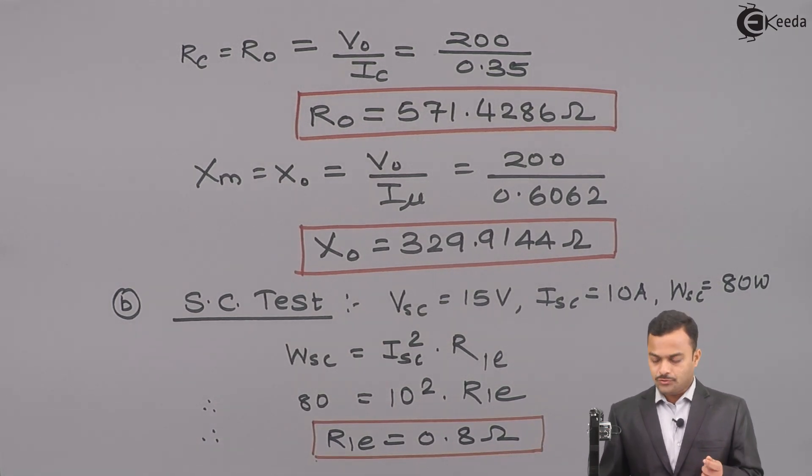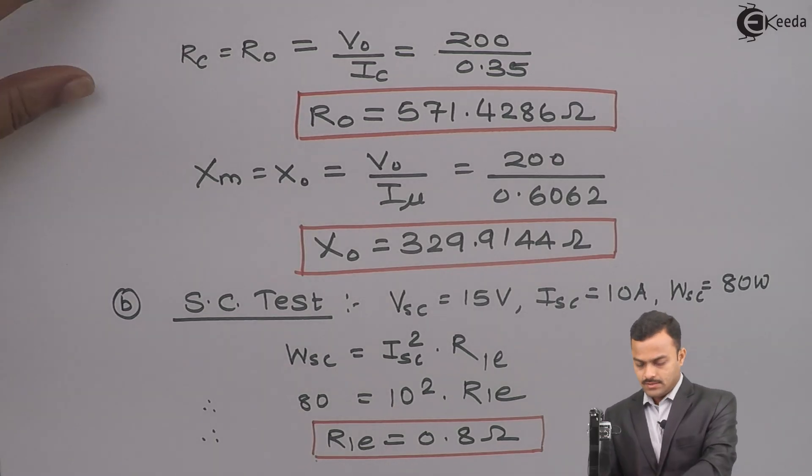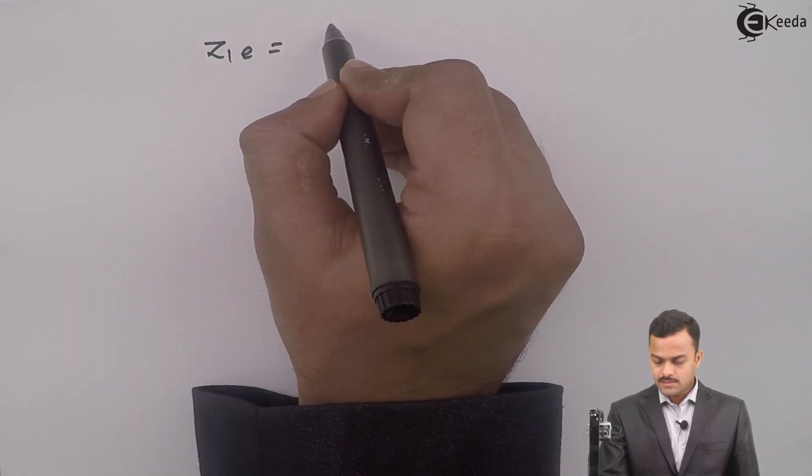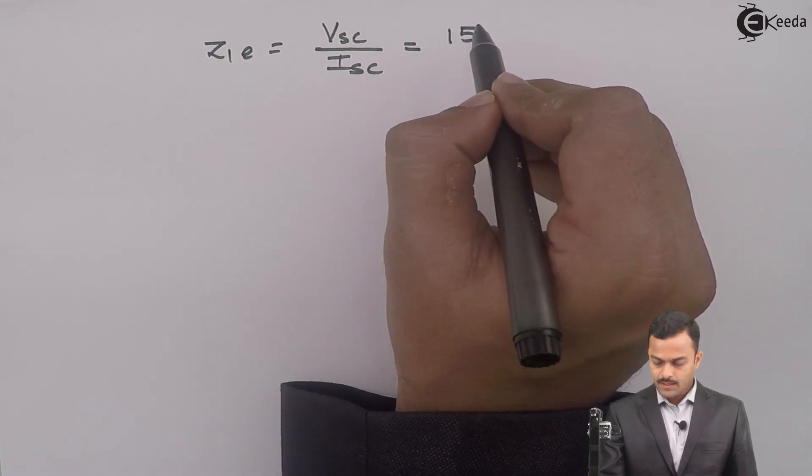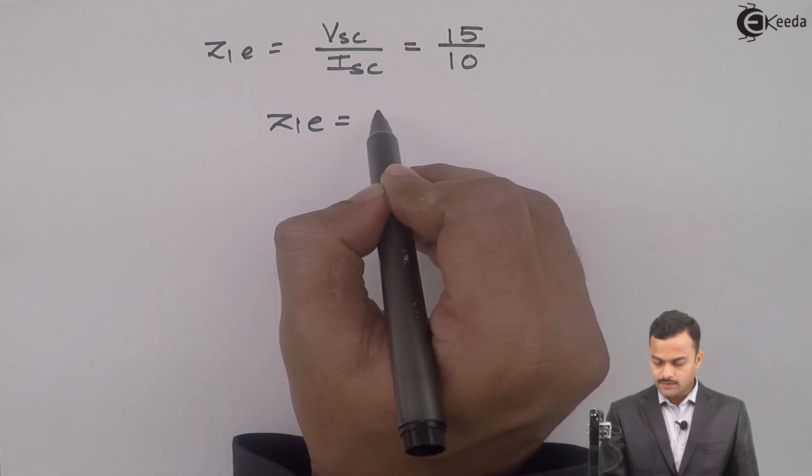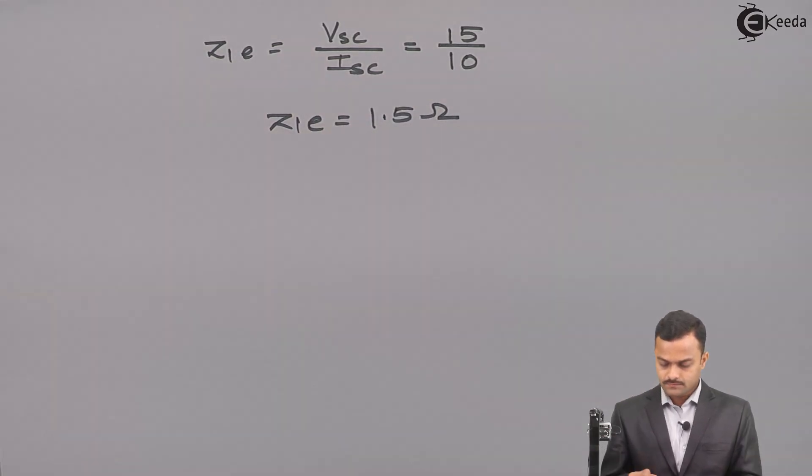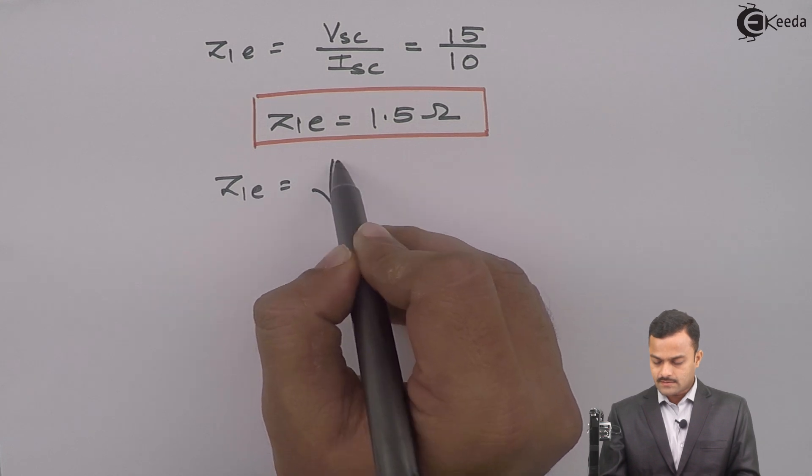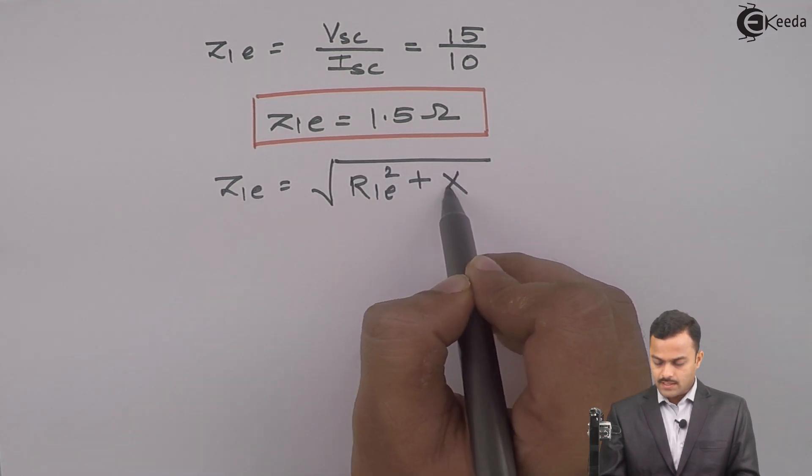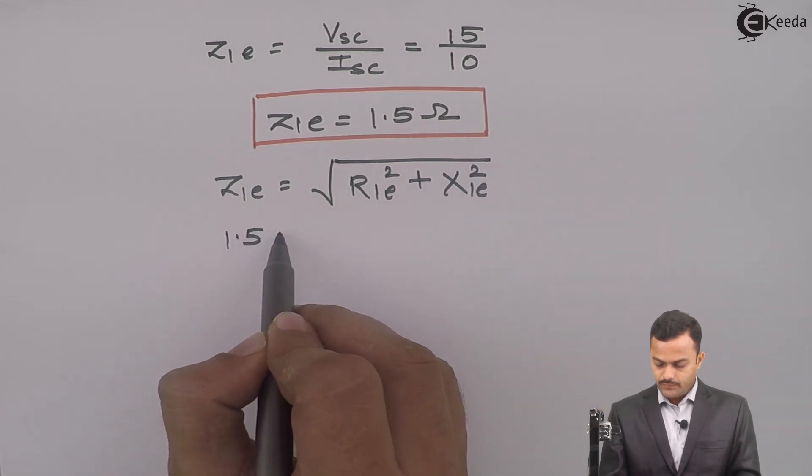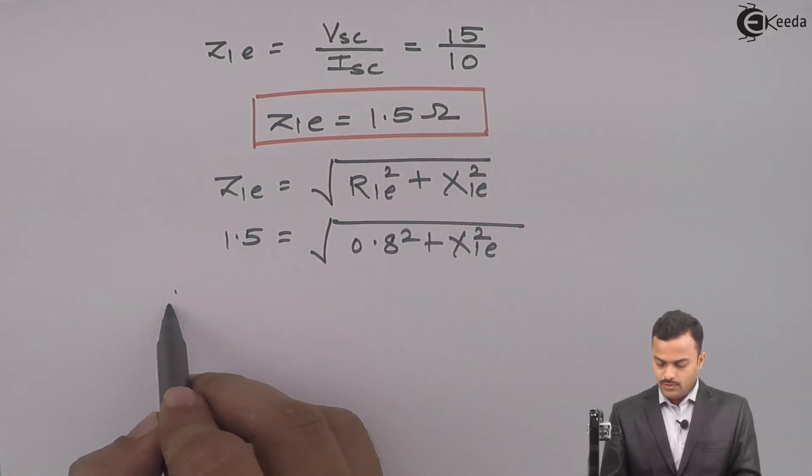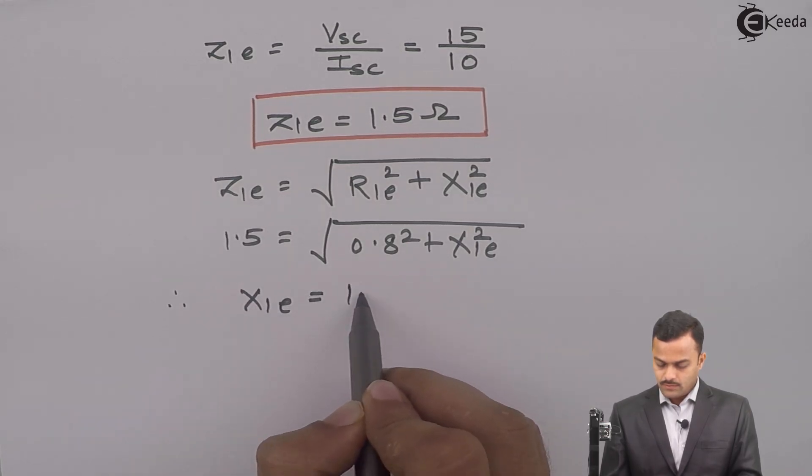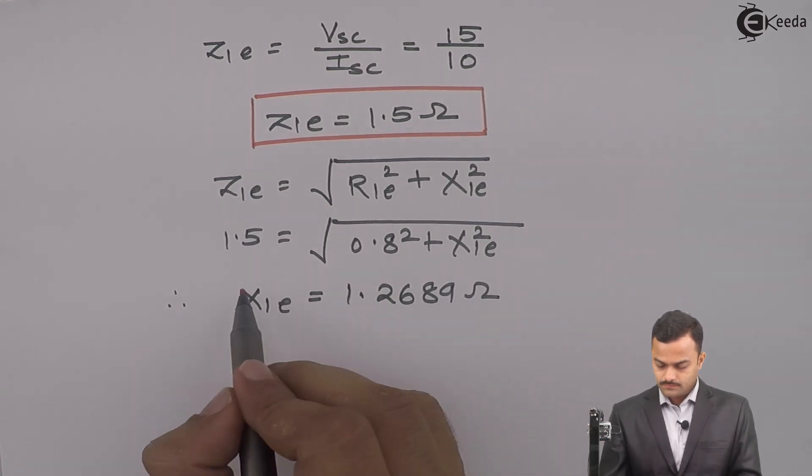Now, I know voltage, I know current, I can get impedance. Impedance Z1E is VSC upon ISC. VSC is 15, ISC is 10. So Z1E is 1.5 ohm. Impedance and resistance is known, so I can get reactance. It is a root of R1E square plus X1E square. So it is 1.5 equal to root of 0.8 square plus X1E square. So only unknown is X1E which is nothing but 1.2689 ohm.